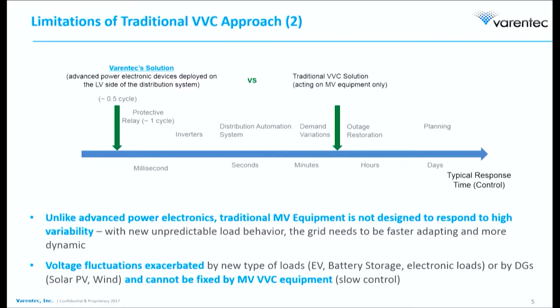The second dimension to this is, how fast does the traditional VVC or CVR react today? You're looking at a system that analyzes and issues control every 15 minutes, and primary or MV equipment like LTCs and cap banks that needs up to a minute to react. Versus the LV Varentec solution, where you have power electronics that, on a sub-cycle basis, monitor and control the voltage near where the customer is.